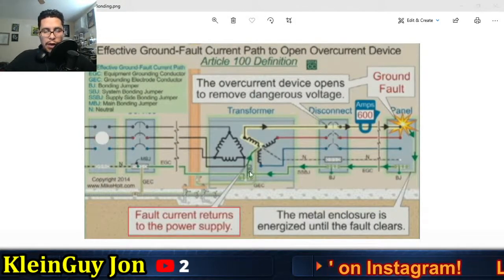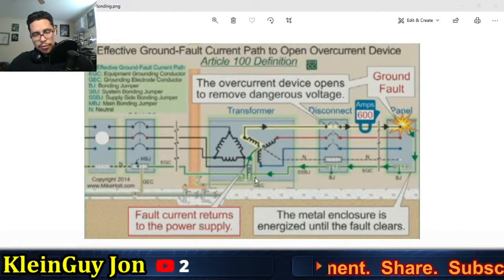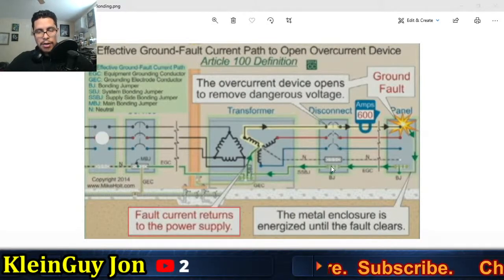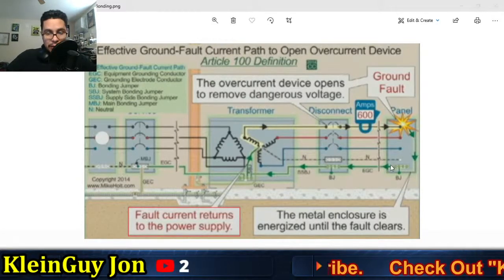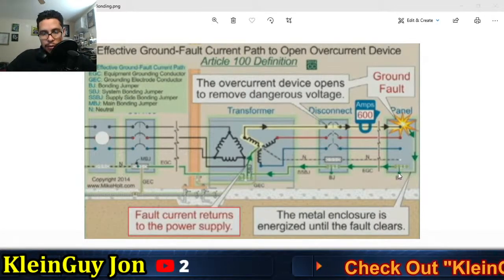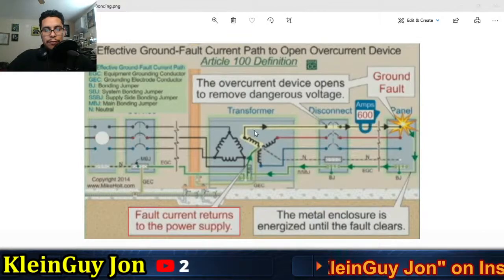Or I'm sorry, if you don't have a system bonding jumper and you have this right here bonded, the grounding electrode conductor bonded from the XO terminal to the structure, and then on your system bonding jumper terminal you have your supply side bonding jumper go into the bonding jumper, you bond it to the frame, then you have your equipment grounding conductor bonded to the bonding jumper, bonded to the ground terminal, and then you have a bonding jumper bonding it to the panel of the frame. What happens when you have a fault?